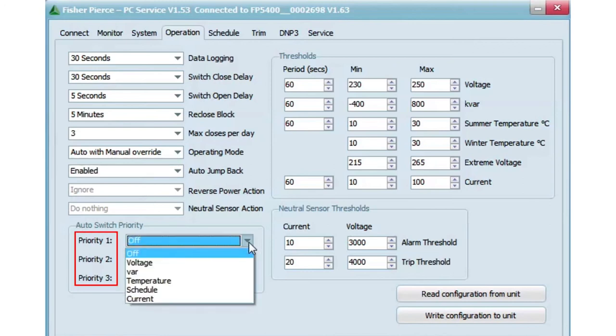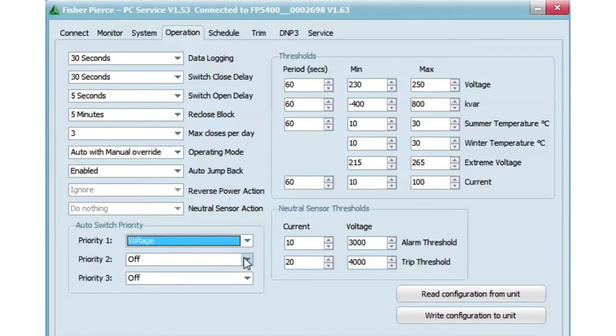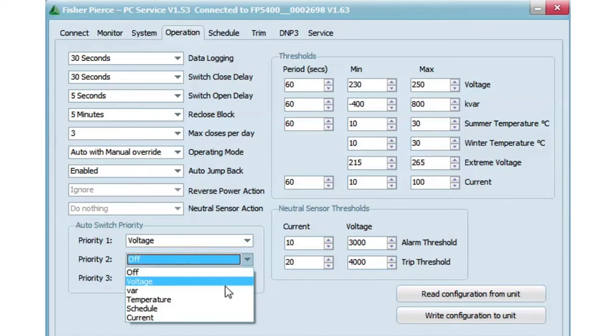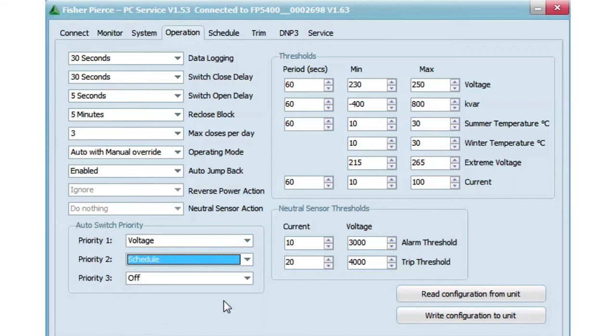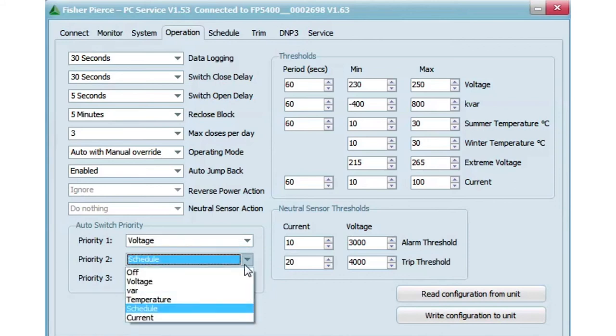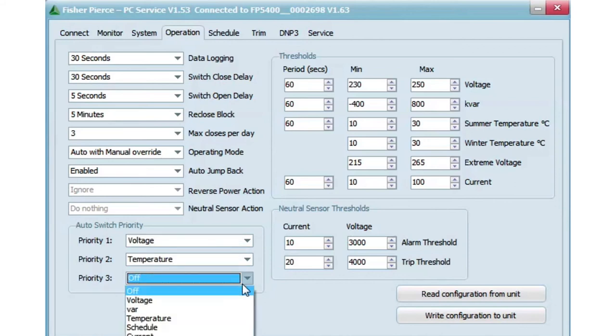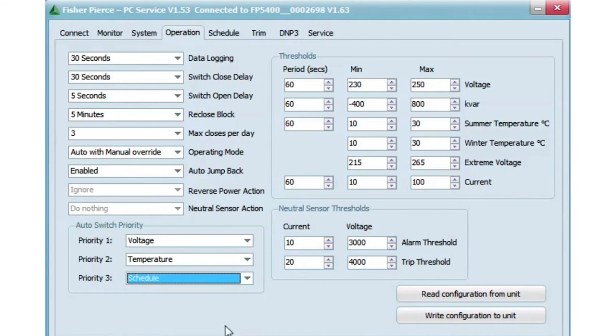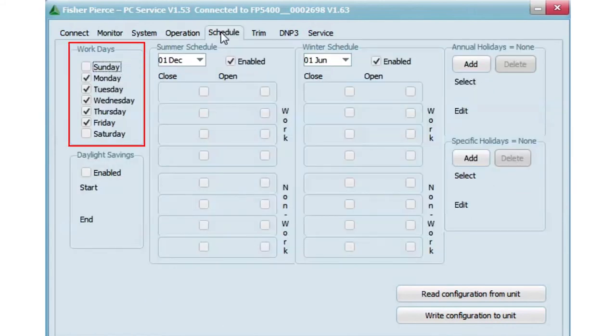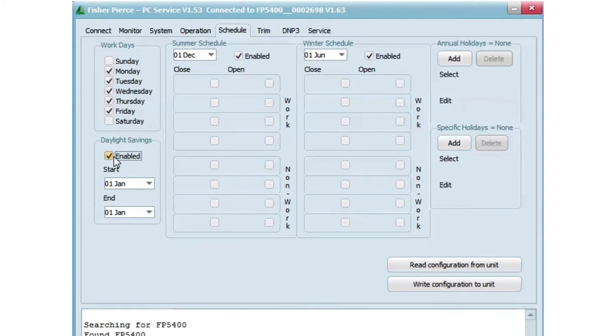Auto priority modes 1, 2, and 3 can be any combination of voltage, var, temp, current, or schedule. With the schedule, you're able to program the days of the week and open and close periods, including holidays and daylight savings.